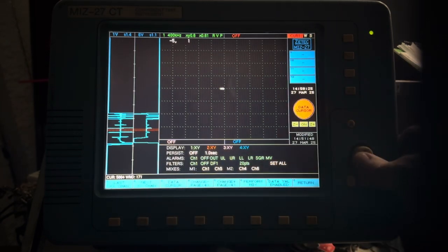And then, let's see here. So that's going to be your 100% hole through wall. There's your 80%. Now you may have noticed already that the amplitude of the 100 and the 80% flat bottom hole from the OD are about the same. That's because the diameter of the 100% hole is a little bit smaller. So the smaller diameter through wall hole and the slightly larger diameter 80% flat bottom hole have about the same metal amount, or volume.